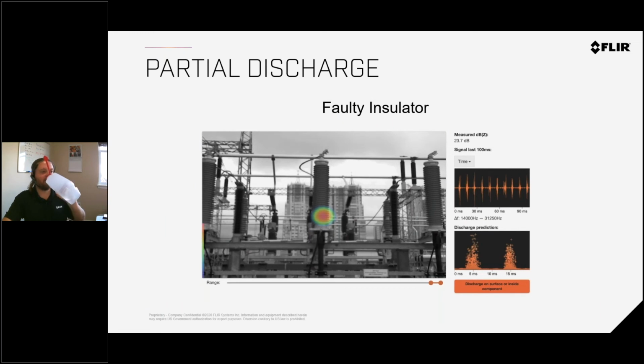Here's an example of a faulty insulator. Through your scan, you might find an image that looks like discharge potentially inside the component. It could be on the surface, caused by a dirty insulator, dirt, bird poop, or something else. Once verified that the component is clean, your next thought should be that this could be an internal problem and cause for concern that needs to be fixed. You'll get that prediction and analysis telling you whether it's discharge on the surface or inside the component. Knowing this, if you can power down the transformer at a time that works into your schedule, you can take a closer look and implement a fix if needed.